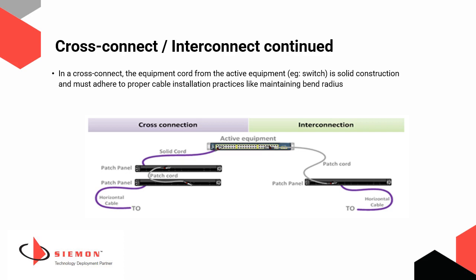In an interconnect design, patching is done directly between the active equipment and the distribution patch panel. This design is quicker, easier, and cheaper to deploy than a cross-connect design and requires less rack space. It is, however, less secure, as patching technicians must have access to both the active equipment and passive patch zone.